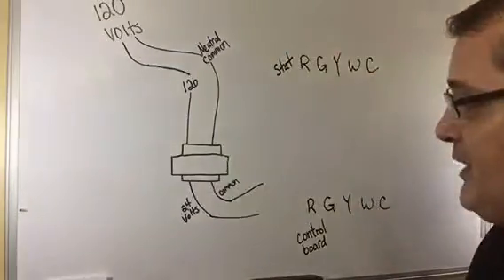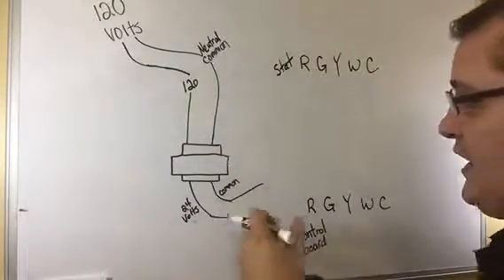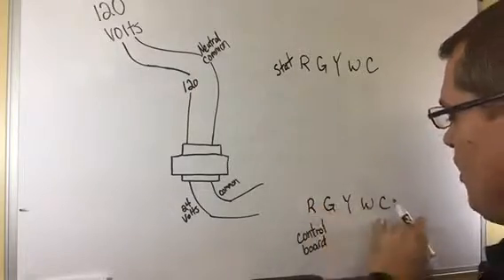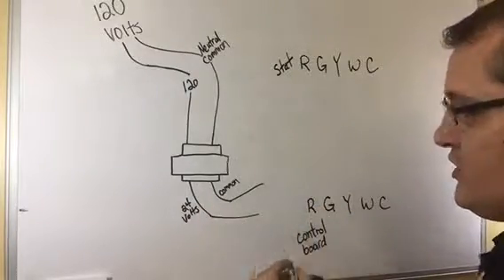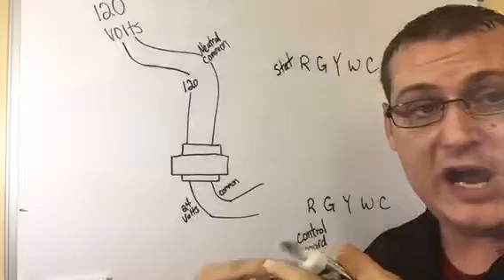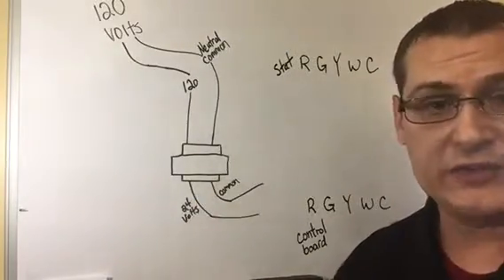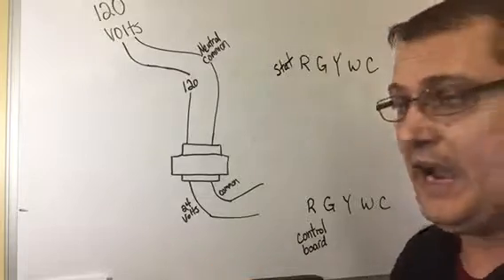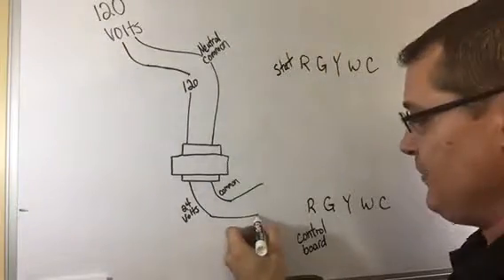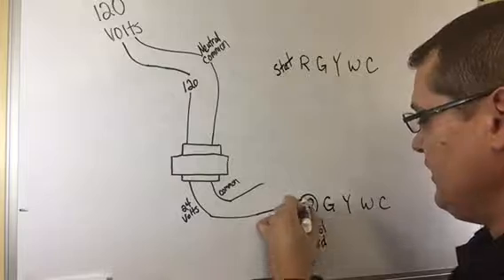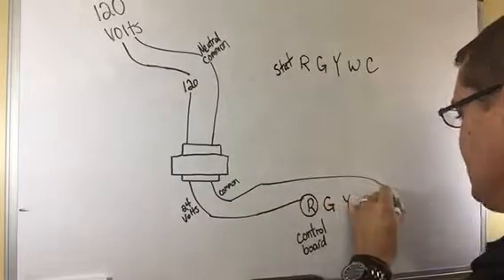What's happening is it may not go directly to R and C, this 24 volts. It may be internally wired in on the control board itself, soldered in through the connections on the back. But ultimately, what's happening is 24 volts is going to R and common is going to C.